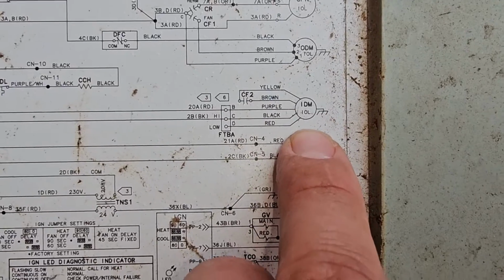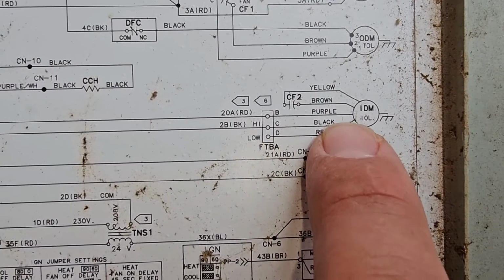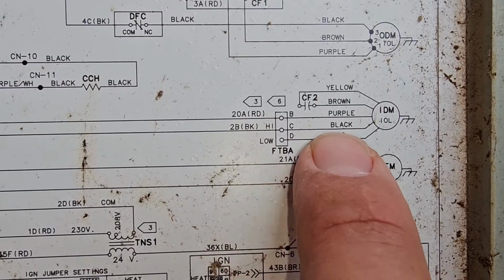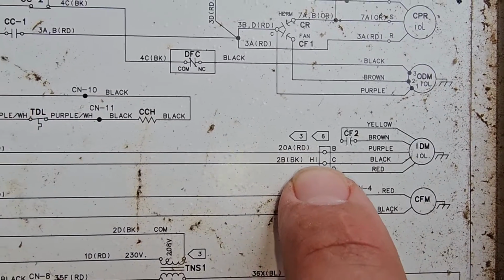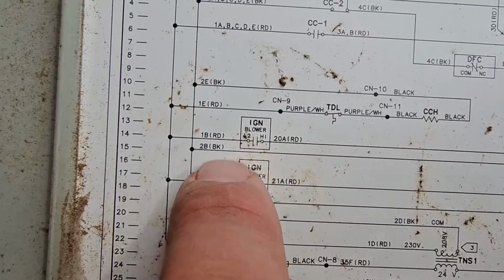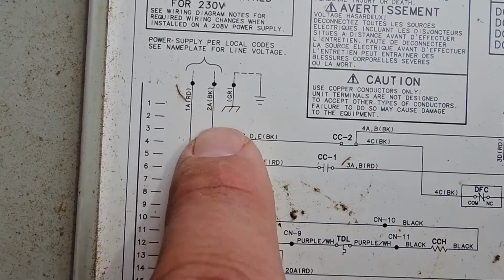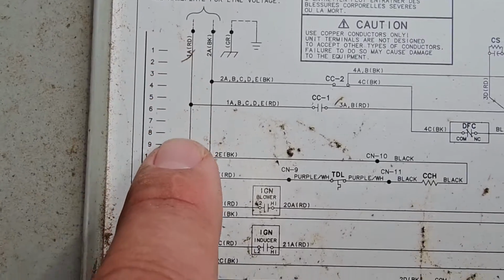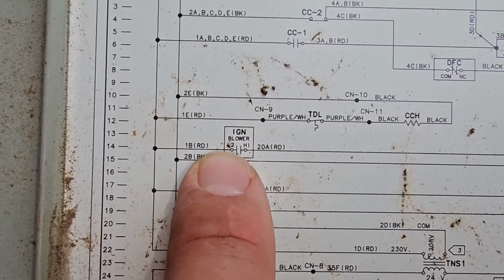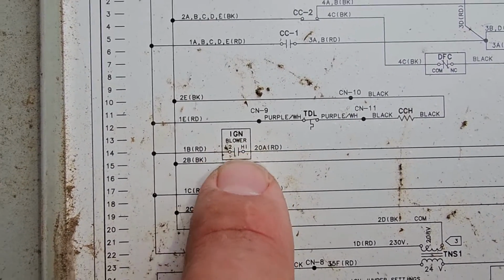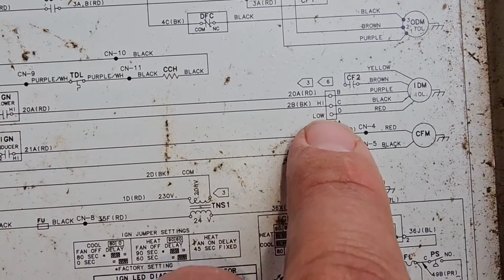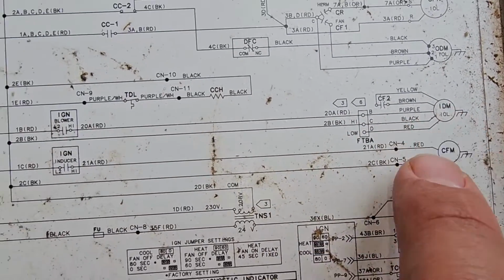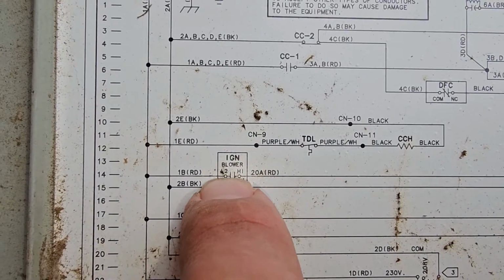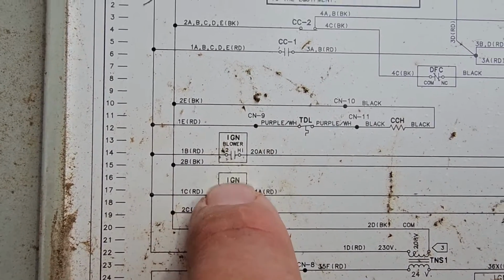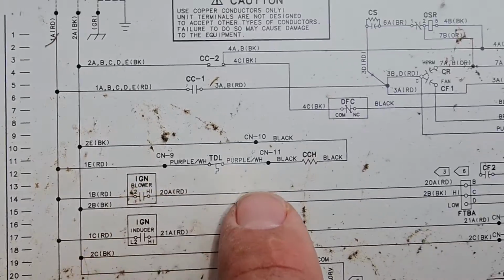See, this means indoor motor. See that? Purple wire goes to B, black wire goes to C, and that black is the high speed, and it goes back to one side of the power. And that other side of the power, that's the red wire, goes to a set of normally open contacts, right? So that black wire always has power going to that side of the motor, right? And then when this side of the power that goes to that motor, the common, when that relay closes, that energizes the motor. So I just want to show you that.